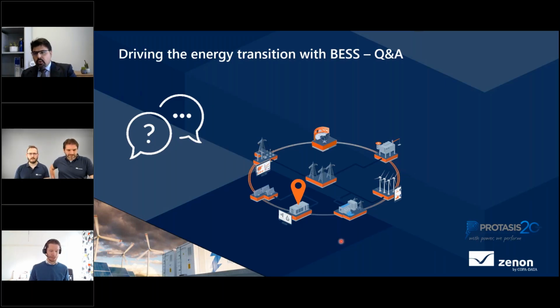We used two protocols. The first is Modbus TCP for the interconnection of the central control unit with the battery system, and we used 61850 for the internal communication between the central control unit and the SCADA system. We selected 61850 because we would like to have reporting functionalities and to make sure that we will receive all data in a quick and safe manner.